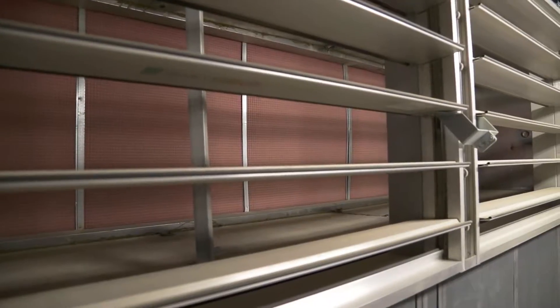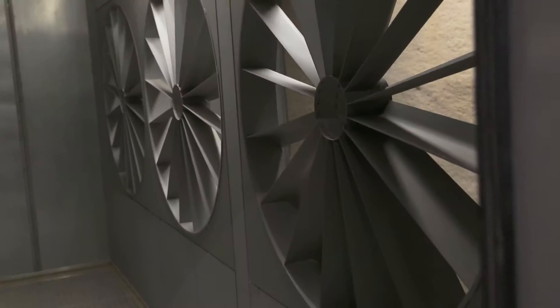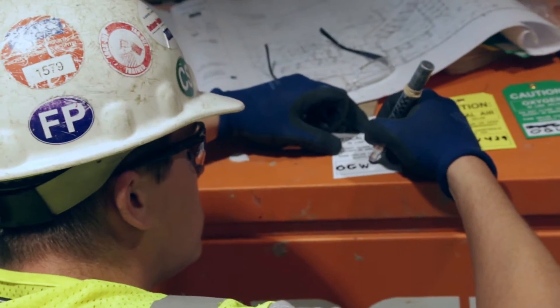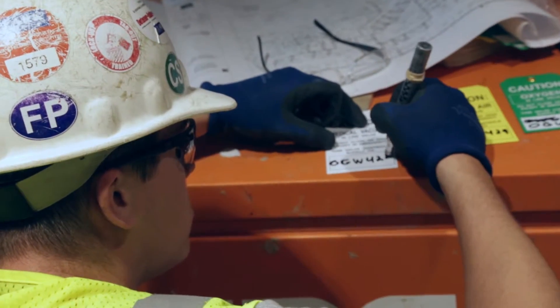These filters are similar to what would be included in a residential HVAC installation but are substantially larger since they handle a much greater volume of air. There are two stages of filtration beginning with a MERV 8 and progressing through a MERV 11 rack. It is critical that no airborne dirt or particulate matter pass into the air supply to the hospital.